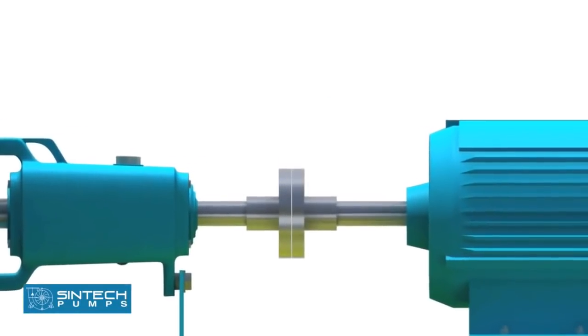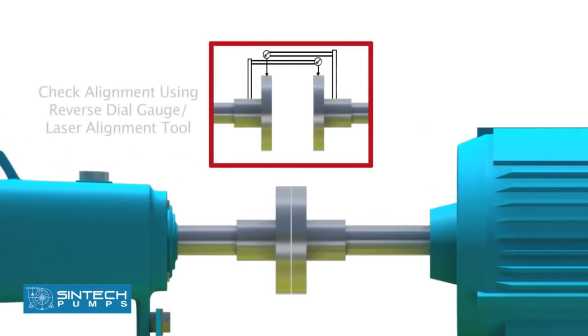In the subsequent step, the pump and the motor are aligned to the final tolerance using a reverse dial gauge or a laser alignment tool.